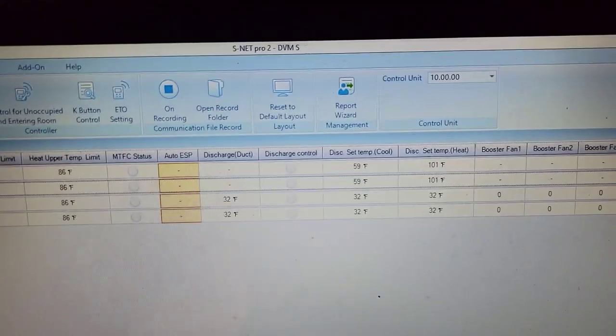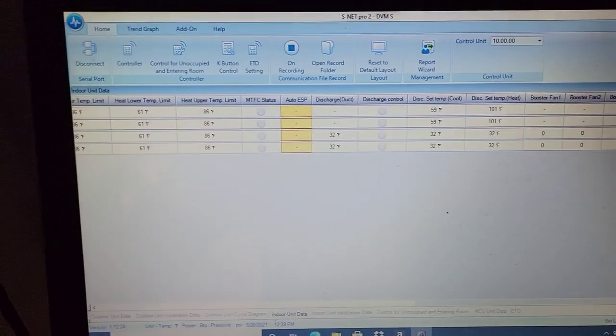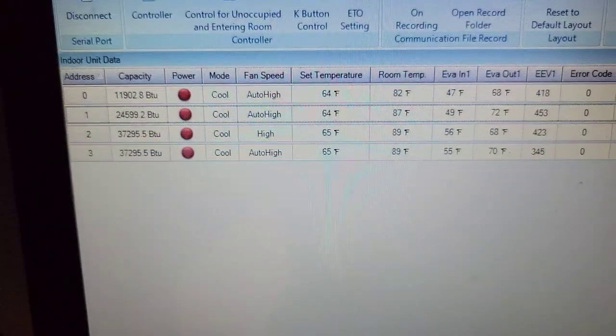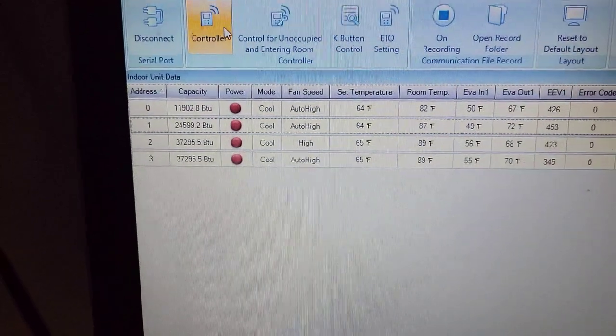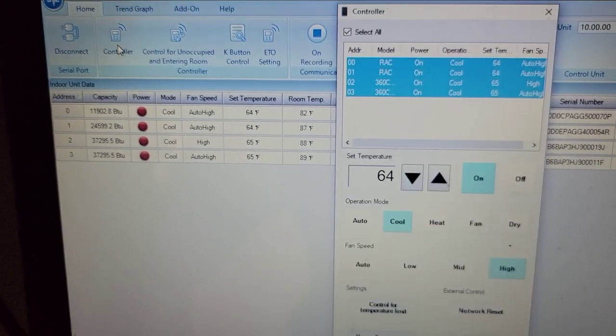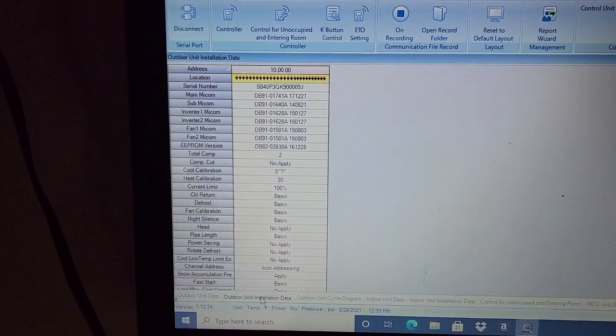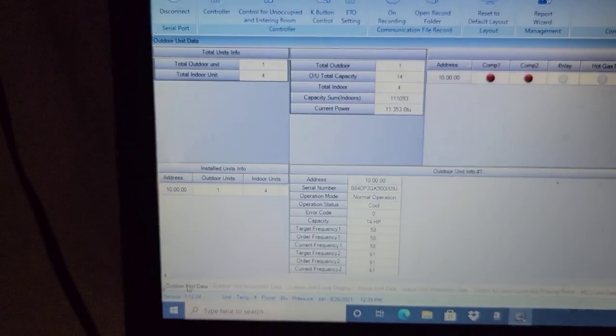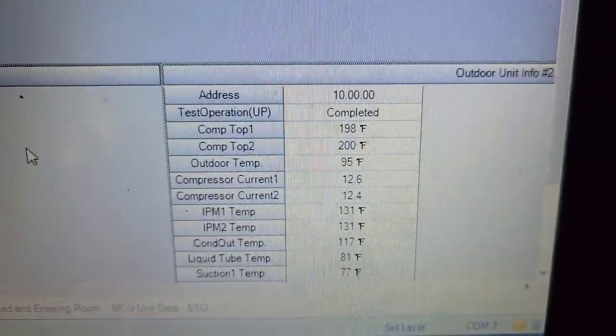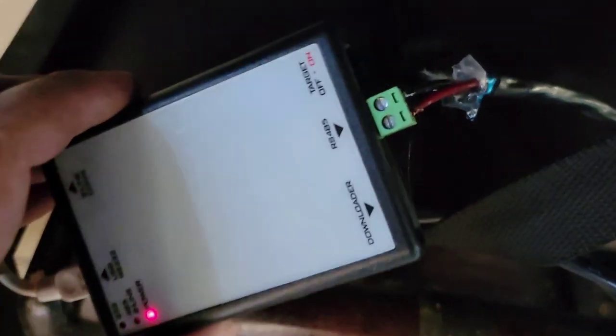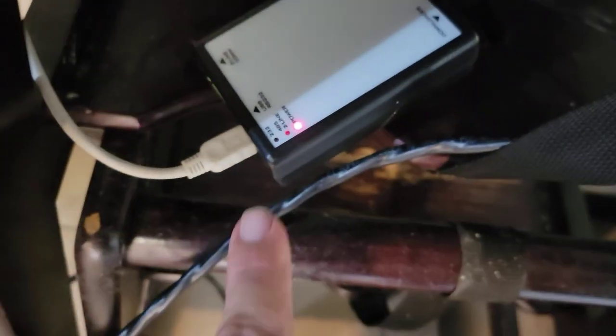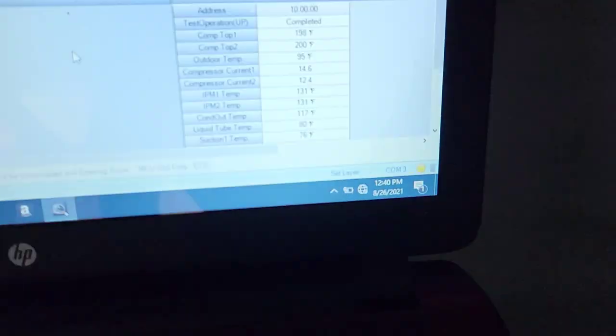Discharge temperature set. We've got 360 cassettes on this, so you can see that right here. It shows what the unit is if we go to controller. See, we've got a couple 360 cassettes. Now we can go to the outdoor unit installation data or the outdoor unit data. Look at the compressor top. These things have two compressors. I'll show you. This right here is my S-NET tool. You can see where I've got that hooked up.